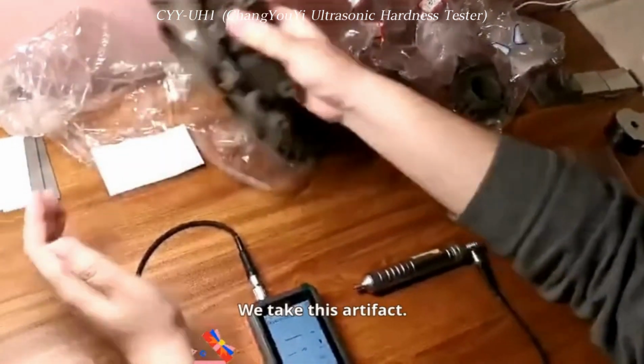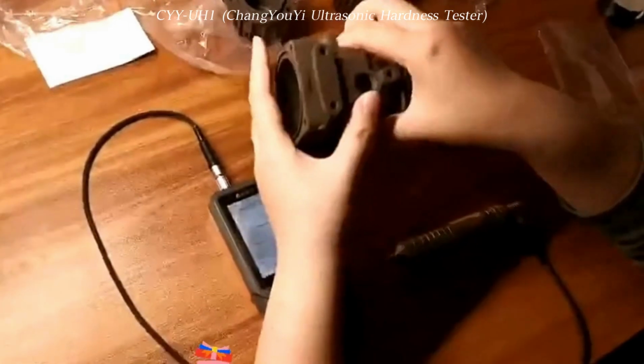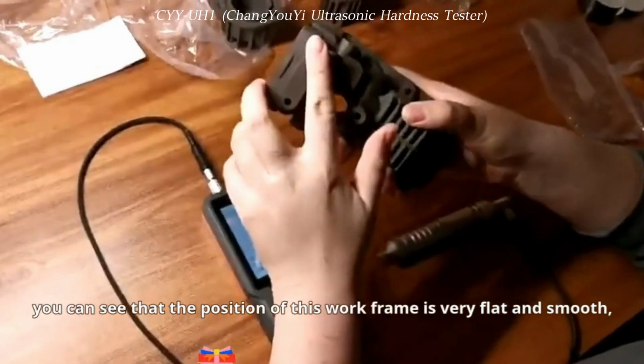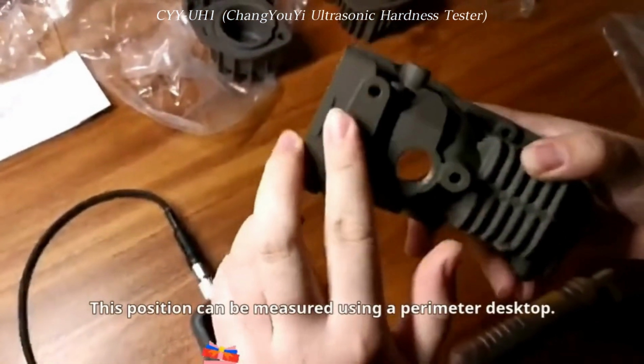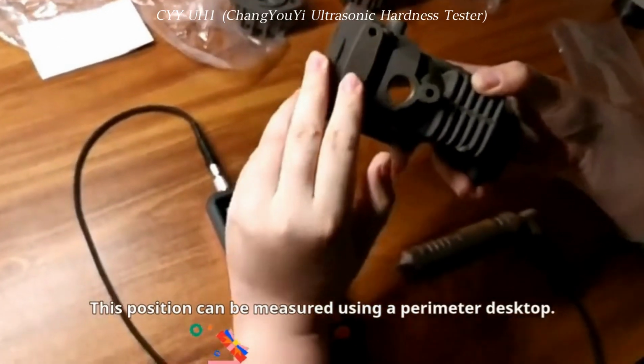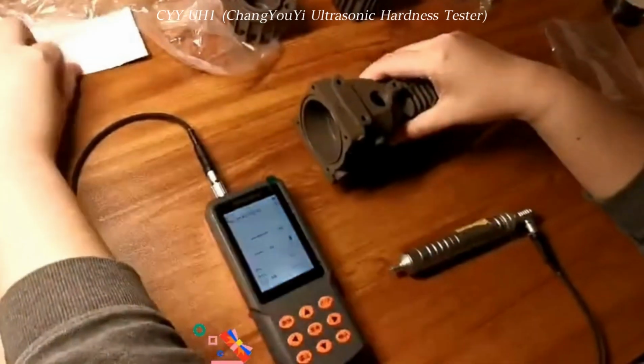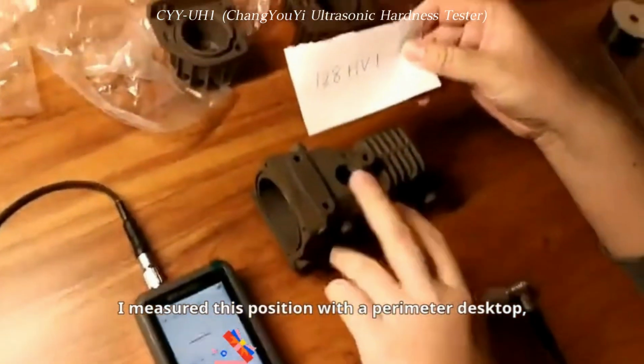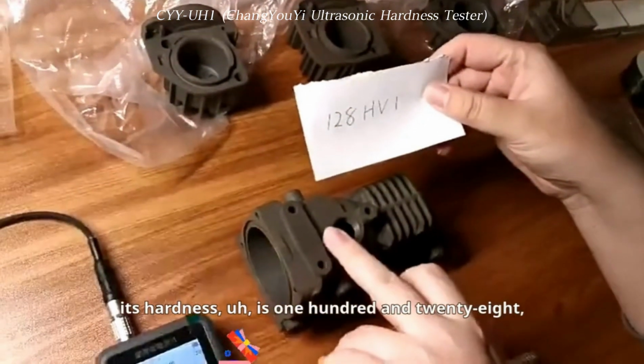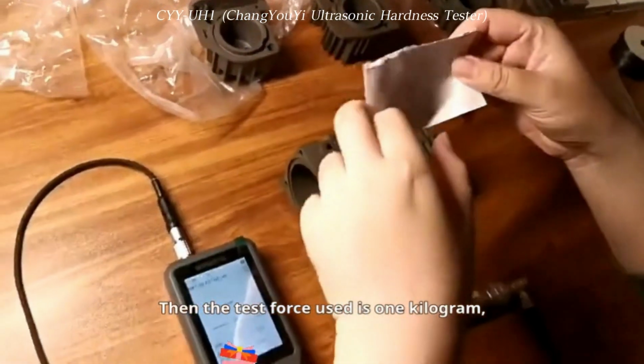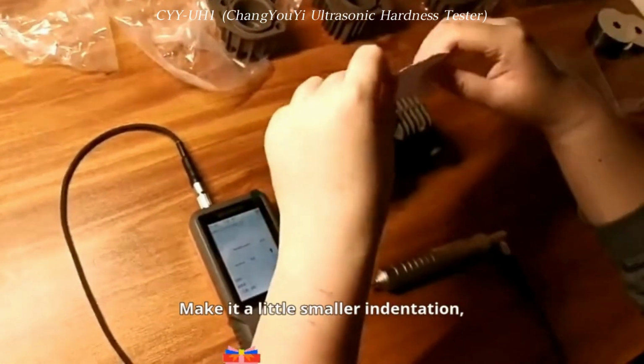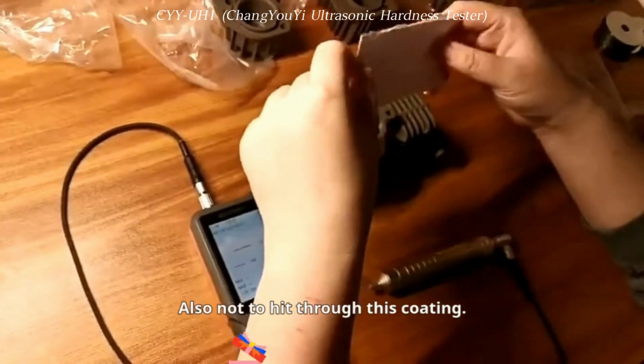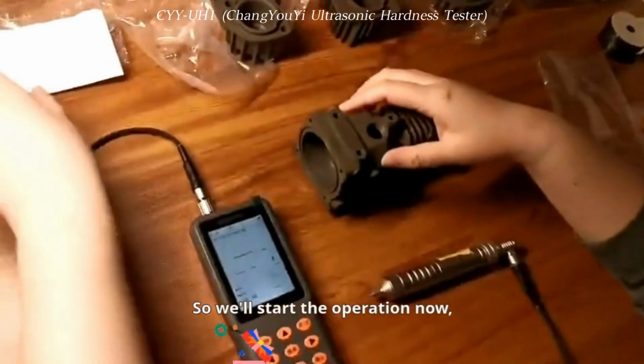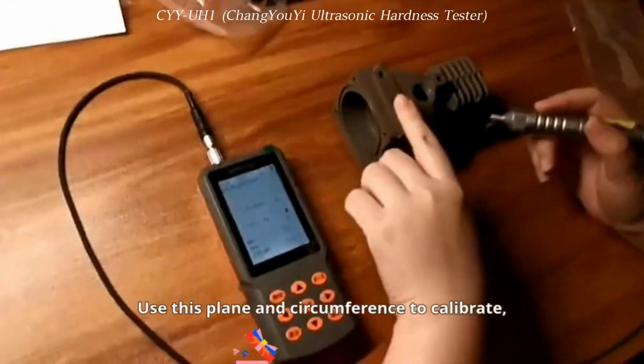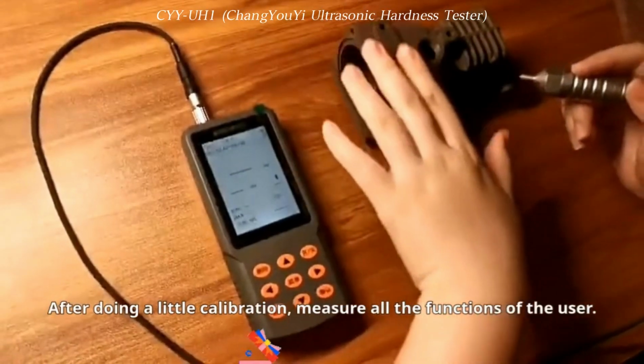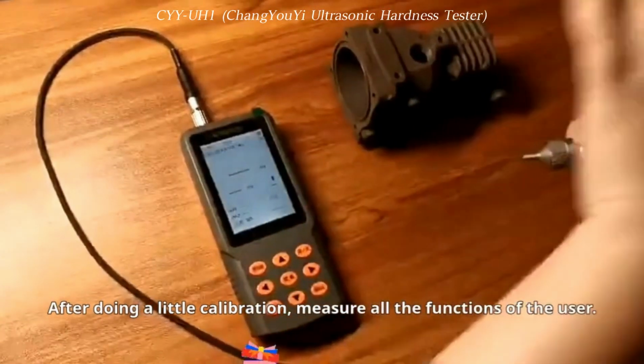First of all, we take this artifact. You can see that the position of this workpiece is very flat and smooth. This position can be measured using a desktop tester. Today, I measured this position with a desktop Vickers tester. Its hardness is 128, and the test force used is 1 kilogram, to make a smaller indentation and not hit through this coating. So we'll start the operation now. We use this plane to calibrate, and after the single-point calibration, measure all the features of the user's part.